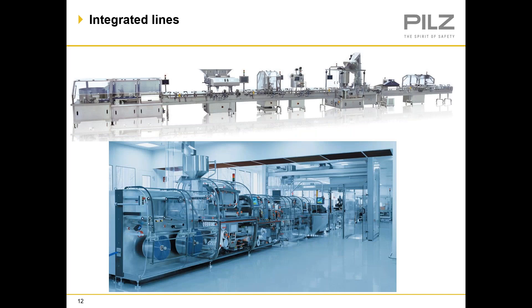For integrated lines, if you're creating a packaging line either as an OEM or end user, you may have a complex assembly and a UK CA mark may be required for the whole line, not individual machines. The UK machinery safety regulations apply to an assembly of machines where they are assembled together to carry out a common function, where constituent parts are functionally linked so each unit affects the operation of others, and they have a common control system. A group of machines connected to each other where each functions independently is not considered an assembly and would not require a UK CA mark.